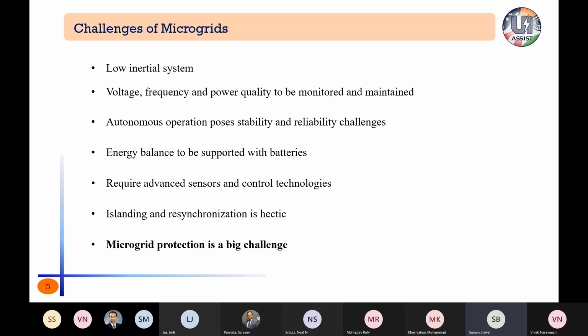The first one is a low inertia system, because in microgrids we have distributed generations that are basically inverter based. So unlike conventional generation, they have very low inertia. So when there is any disturbance, it disturbs the voltage and frequency. That brings challenges to the utility to maintain power quality, and stability and reliability challenges are there in microgrids. And to support the load demand, we need storage, including batteries or supercapacitors, and also some advanced sensors and control technologies should be there. Islanding and resynchronization are problematic, and obviously microgrid protection is a big challenge.